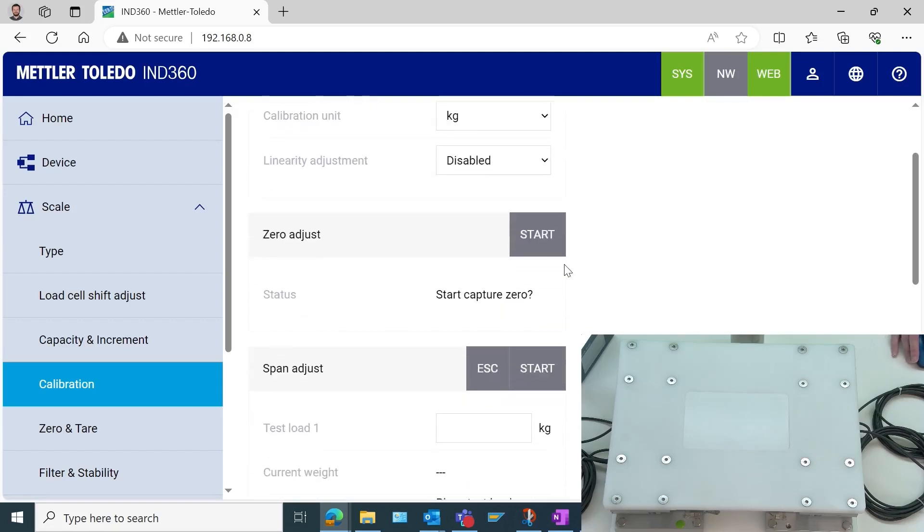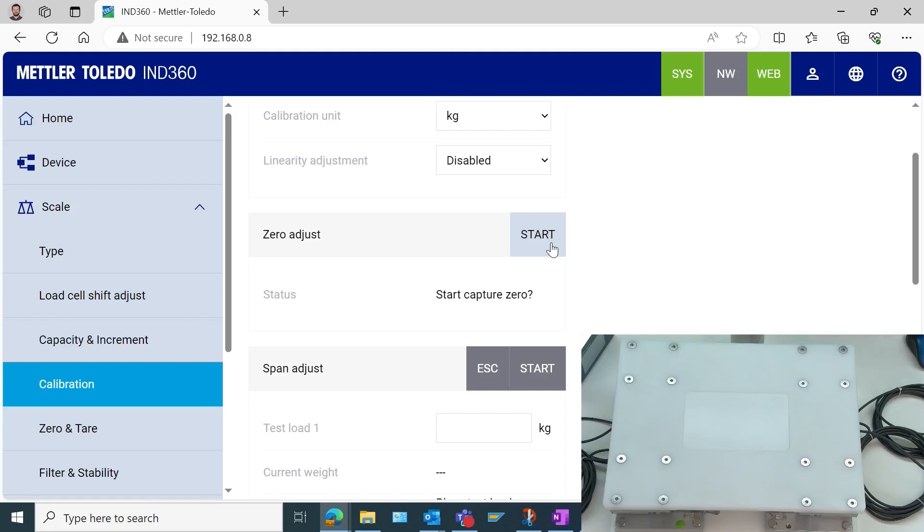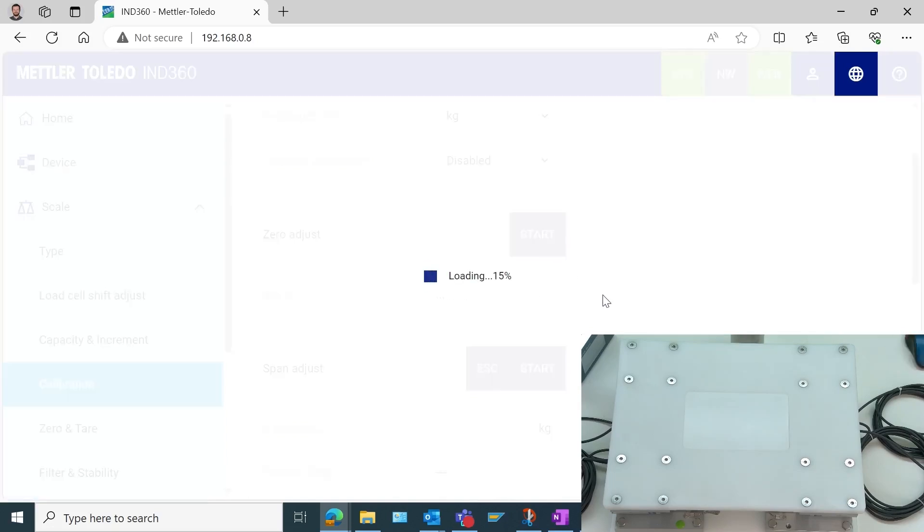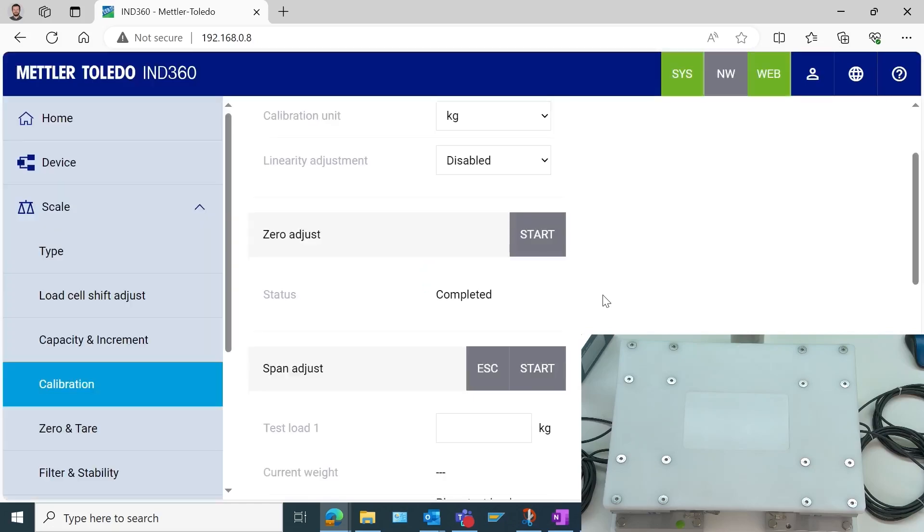The first thing we want to do is a zero adjustment. Anything that's going to be permanently on the system, so if there's a tank permanently attached, we want that tank in place. But for this one, we're saying that this platform here is the permanent scale system. So we say this is our zero adjustment point. Let's go ahead and start that. And that is now completed.